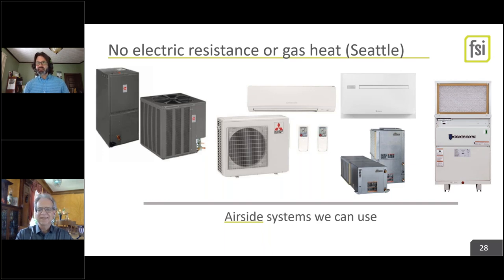Airside system. Yes. So what does this mean? And it shouldn't be no. It's very limited situations. You are allowed to use a little electric resistance, but it is a little, teeny little things. So what it looks like is, oh, look, it's the same systems we've already been talking about. Split systems, split heat pumps, package terminal units, mini splits, and then that dual duct version, water source heat pumps. These are all viable options for heating without electric resistance or natural gas heating.